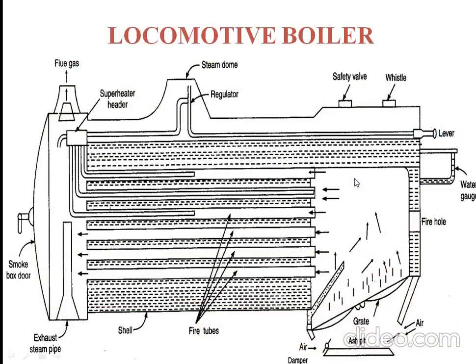Looking at the 2D diagram: this is the grate over which we are burning the coal. We can see the damper or arch — it is used to deflect the flue gases in the upward direction and at the same time prevent ash from entering the fire tubes. There are 6 fire tubes here. The flue gases move from right to left through the tubes, and from the left they escape to the atmosphere through the chimney. The dotted line is the water line.